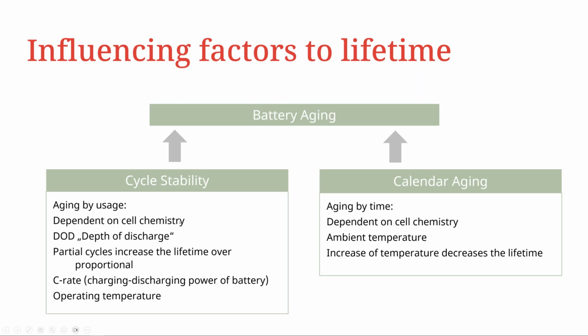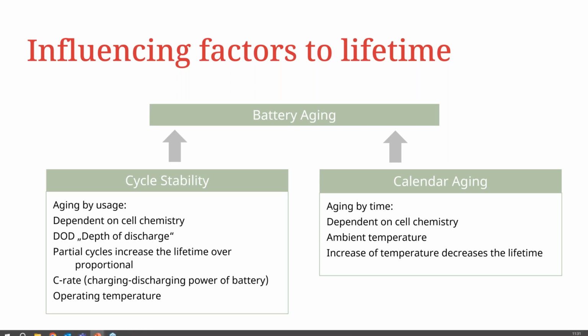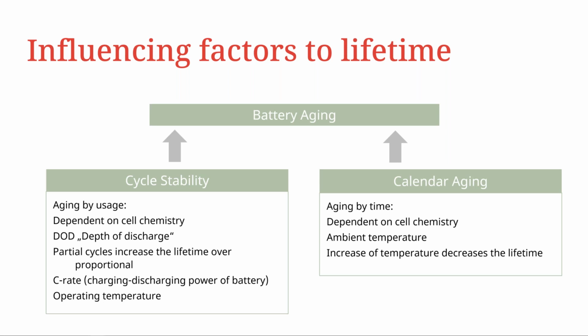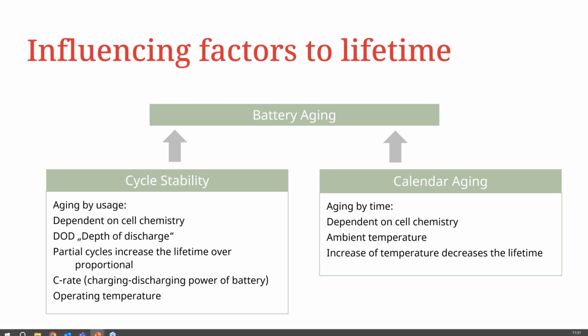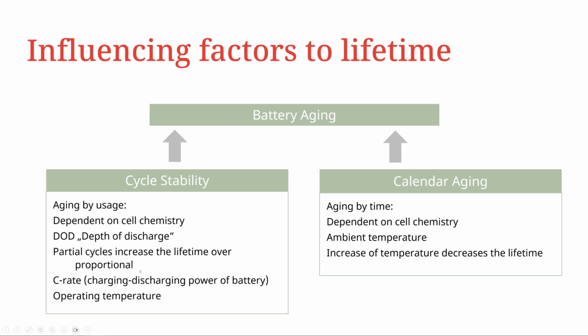Another influencing factor is the DOD, or depth of discharge - the amount to which the battery is discharged and then recharged. Another influencing factor is that partial cycles increase the lifetime over-proportionally. Another thing is the charging rate - the charging/discharging rate power of the battery itself - as well as what Cyprian has just touched on, the operating temperatures. Obviously, if the battery is at a much higher temperature, this will have an influence on the cycle stability, and also if the battery is too cold, it also plays a factor into the cycle stability.